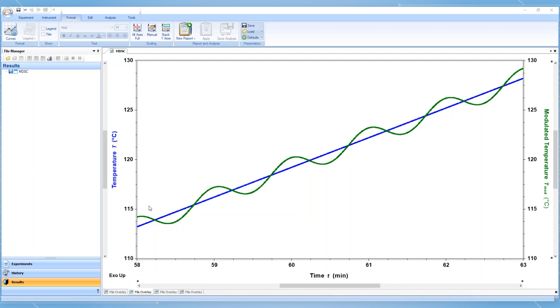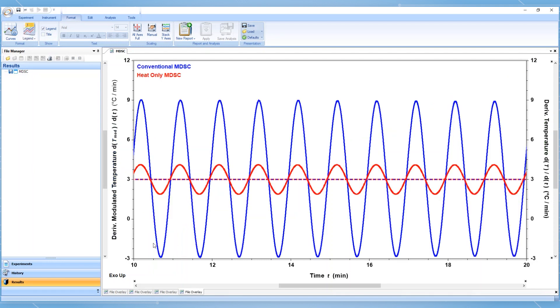During a conventional MDSC experiment, the instantaneous heating rate is both heating and cooling sinusoidally around the average heating rate. When studying melt or crystallization transitions, it is undesirable to have instantaneous cooling. This is when a heat-only MDSC experiment is appropriate. All that is required by the user for these experiments is to select the desired average heating rate and modulation period. The TRIO software will provide the proper amplitude for that average heating rate and modulation period, which will result in the instantaneous heating rate never dropping below zero degrees per minute.